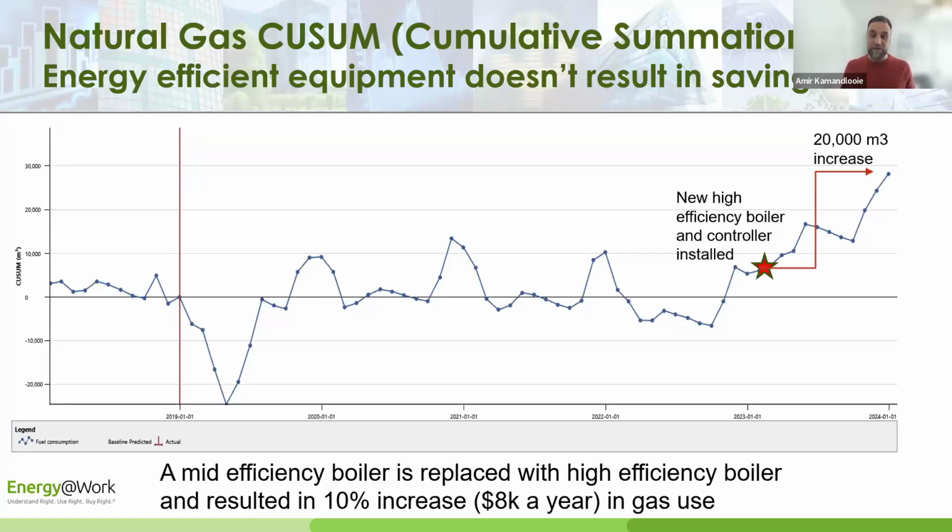It was a good example of what we can do in order to address this issue now that we know our condensing boiler, or the investment we made, is not resulting in what we were expecting. So a bunch of issues came out of it. So we are putting in a finding list and letting them know. So they are going to make probably a very small investment in order to make things tuned and hopefully up and running in the best performance that they could.